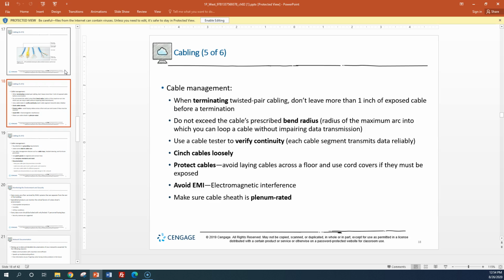Terminations, if they're not done right. I just saw a facility the other day, and they use what's called a patch panel, and you've seen examples of it. What you want to do with those twists is minimize how far you untwist it, because the more you untwist it, the less you retain that ability. In this particular facility, for ease of use, they stripped back about 3 feet on each cable and untwisted it all and then put it into the patch panel. And then bundled it all together with zip ties and tape. I've never seen anybody do that before. Every day it's a new day.